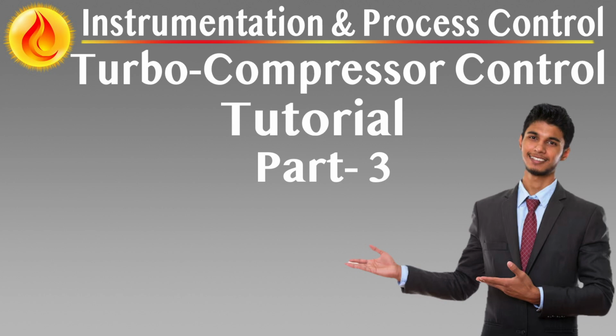Controller decoupling. Logic ensures that anti-surge actions on one stage do not interfere with adjacent stages or parallel compressors. This isolation maintains responsiveness and avoids control conflicts. Startup behavior. During compressor startup, all anti-surge valves are overridden to full open until the compressor reaches minimum stable speed. Control is then smoothly transitioned to active anti-surge logic.